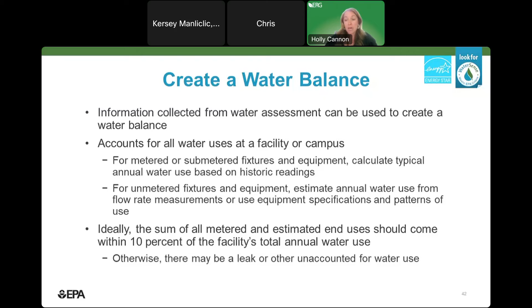For example, I may use irrigation sub-meter information to estimate how much water is used outdoors, and I may calculate how often staff flush the toilet, how long they shower, and how much they use the faucet to estimate restroom water use. I add together all the measured and estimated water end uses, and that should come fairly close to the facility water use baseline calculated at the beginning. If the sum doesn't come within 10% of total water use, you want to look for an unidentified source, a leak, or some other issue needing investigation.